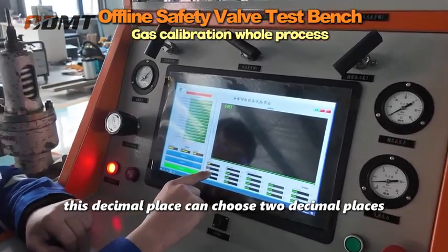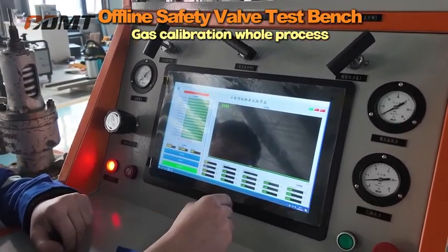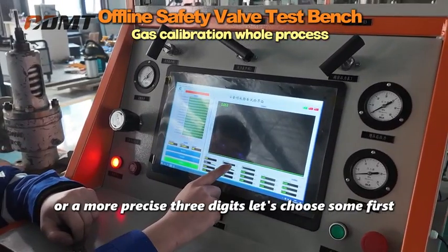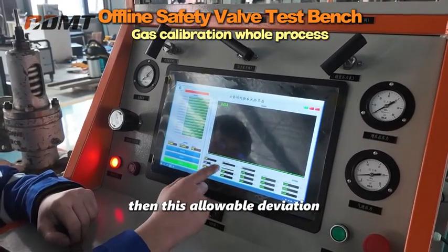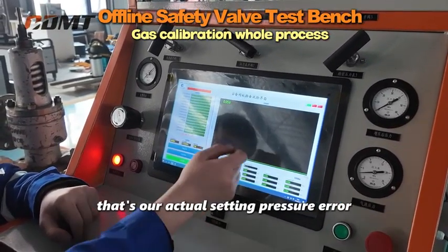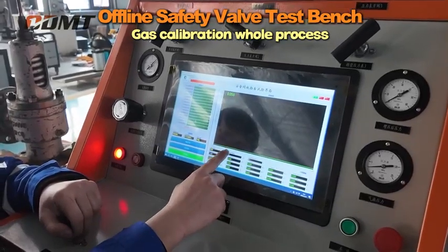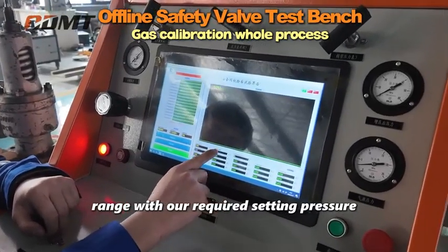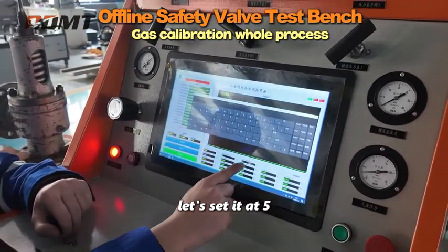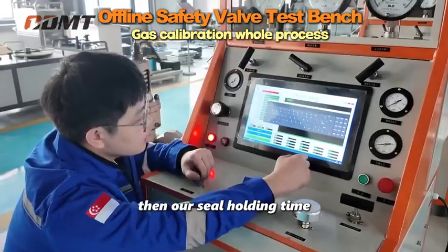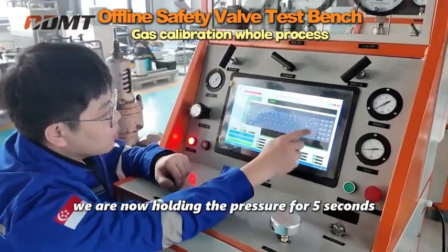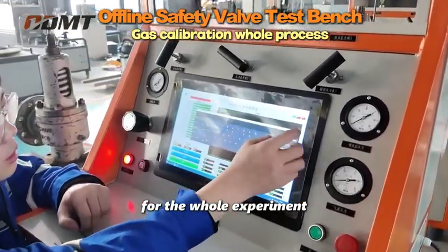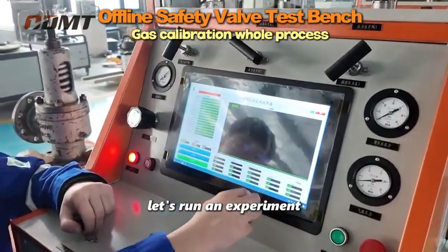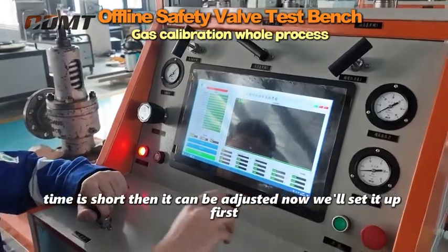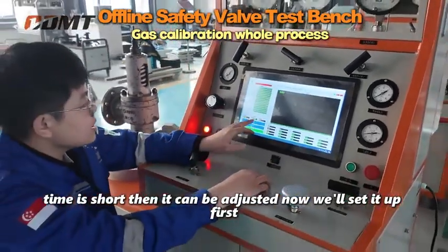This decimal place can choose 2 decimal places, or a more precise 3 digits. Let's choose 3 first. Then, this allowable deviation is the error range between our actual setting pressure and our required setting pressure. Let's set it at 5%. Then our seal holding time. We are holding the pressure for 5 seconds. Since we are running an experiment, our holding time is short. Then it can be adjusted.